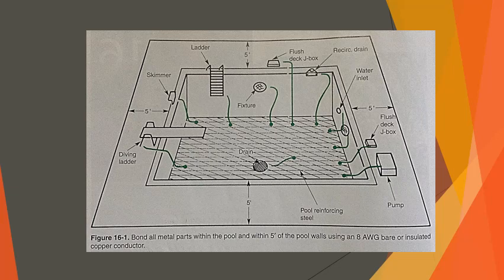Metal parts within the pool walls, including the shells for wet niche fixtures. And metal parts of the pool structure, including the reinforcing steel, steel decking, ladders, and diving board supports. Also, accessory equipment including pump motors, fittings, conduits, piping, and skimmer components. The only job of the bonding conductor is to interconnect the metal parts.